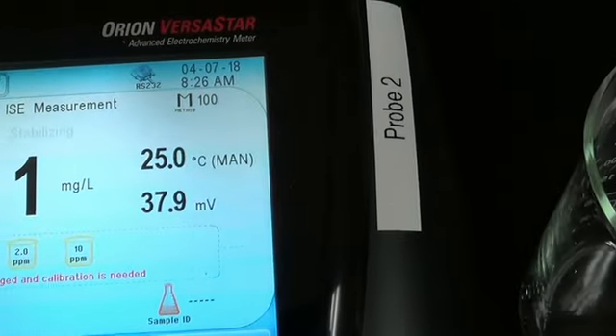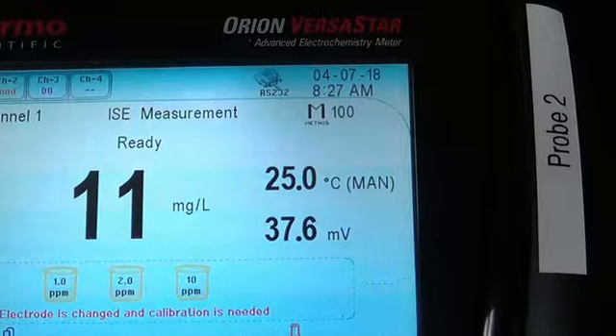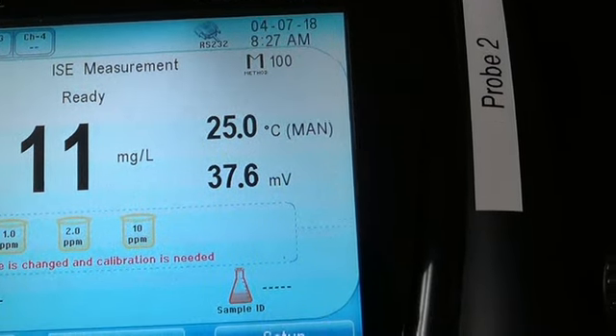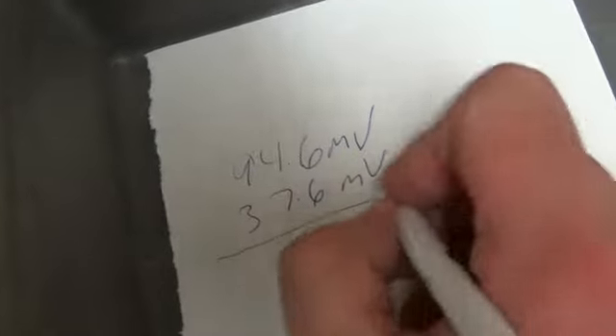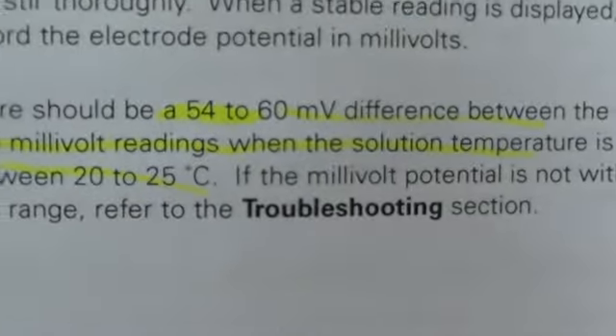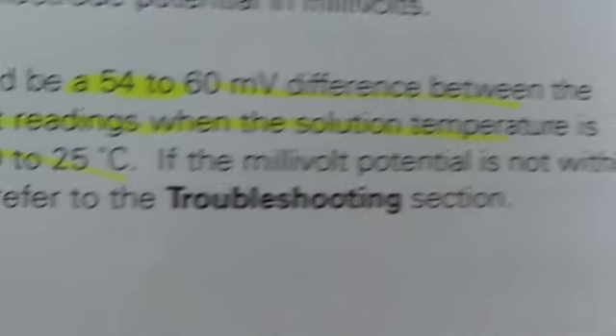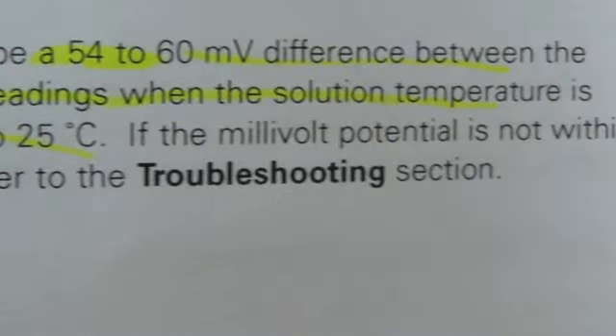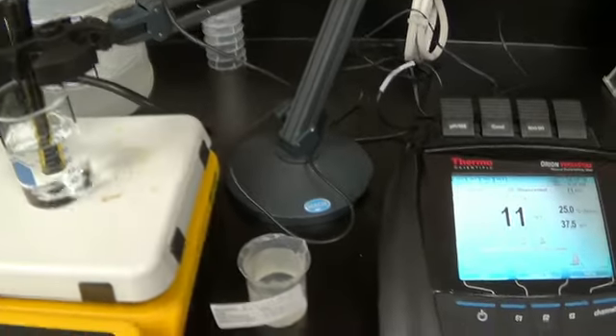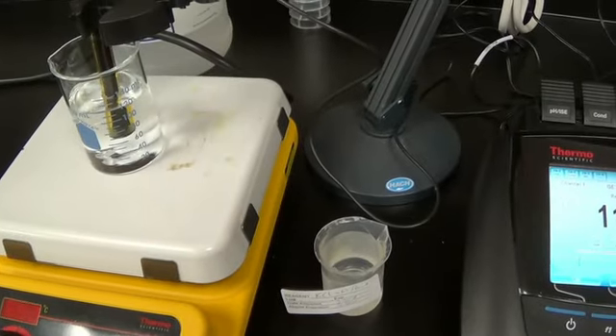And wait for that to stabilize. Alright, that's stabilized at 37.6 millivolts. 37.6 millivolts. I'm going to subtract it. 57.0. Alright, looking at the book, there should be a 54 to 60 millivolt difference between the two millivolt readings. I'm very happy. I'm going to rinse off the probe and get ready for my calibration.